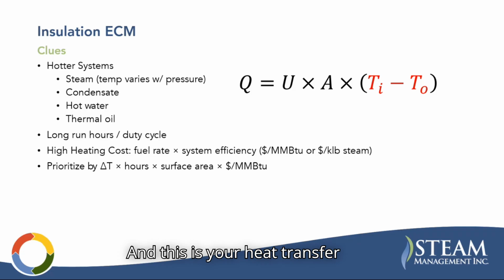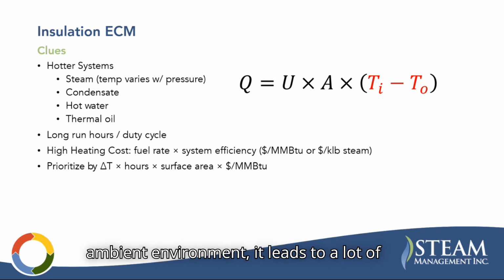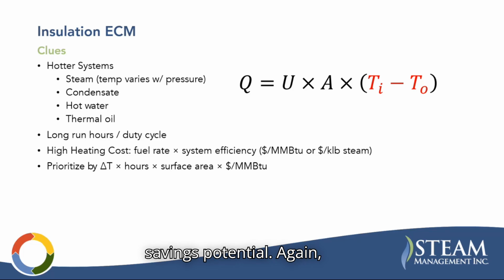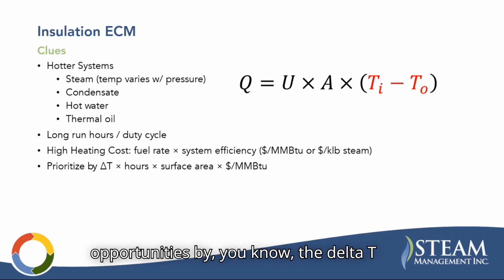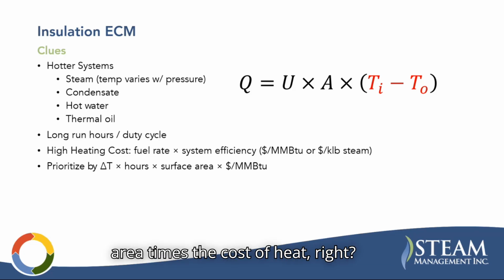And this is your heat transfer equation, right? Everything else being equal, that larger delta T between a hot steam system and the ambient environment leads to a lot of savings potential. Again, long run hours are good. High heating costs: the poorer efficiency the system has, the better payback insulating it has. And then you're going to prioritize the opportunities by the delta T times the operating hours times the surface area times the cost of heat, right?